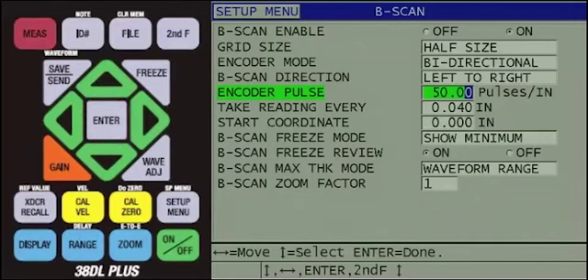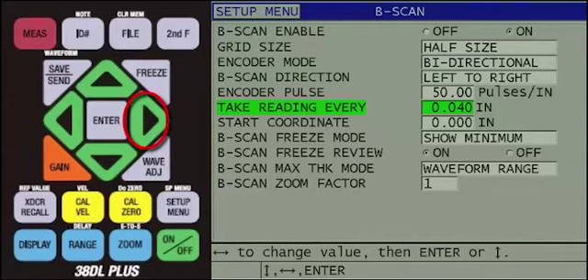Since we are using the Olympus B-scan-ENC Buggy, we will use the default encoder pulse of 50 pulses per inch, or if you are using metric units, it would be 1.97 pulses per millimeter. Then press the Enter key to highlight Take Reading Every. As discussed in previous slides, having the instrument make measurements every 0.040 inches, 1 millimeter, will require the user to move the Buggy quite slow, since the gauge needs to take a reading every 0.040 inches, or 1 millimeter. For this demo, we will change this setting to 0.100 inches, 2.54 millimeters, by pressing the right arrow.